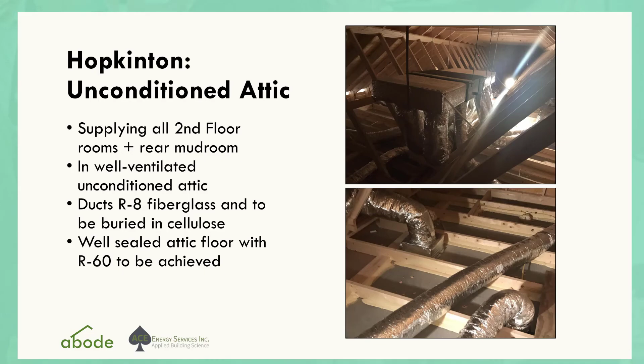So here's the attic. As I said, if you're going to put a unit in an attic, be careful. This one has very good attic ventilation, and we're going to bury those ducts in cellulose, giving them an R60 floor. We laid the ductwork as low as possible on the floor, so when we insulate the attic floor we can cover the ductwork and add to the R value already on the ducts. But there was no other way to do this with this modular home, we had to put that unit in the cold attic.